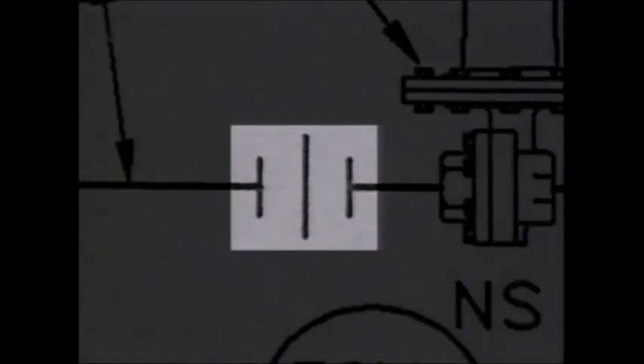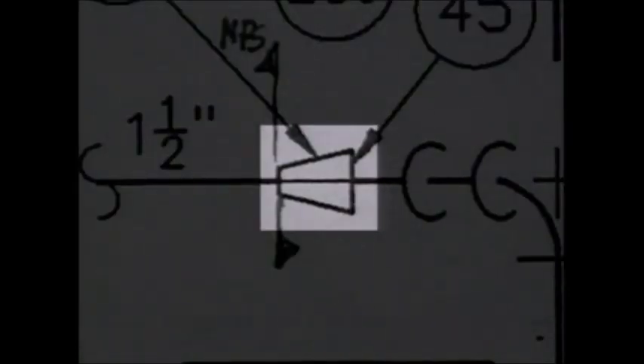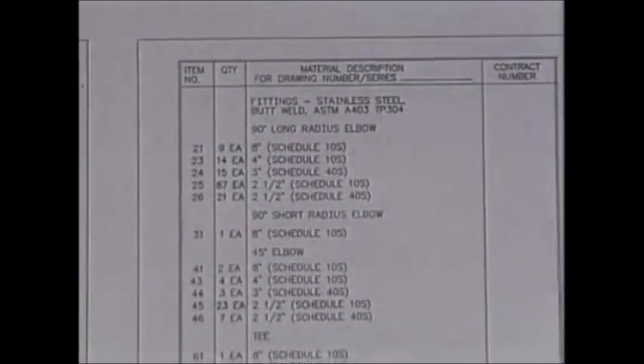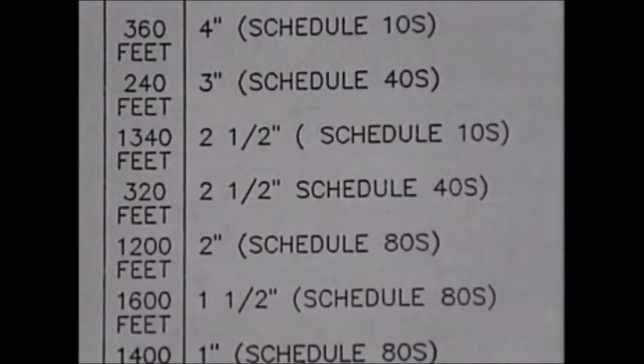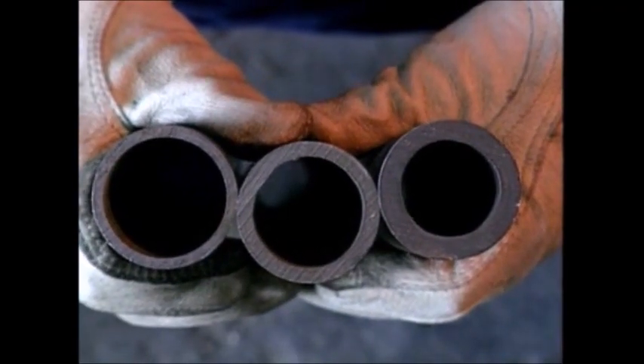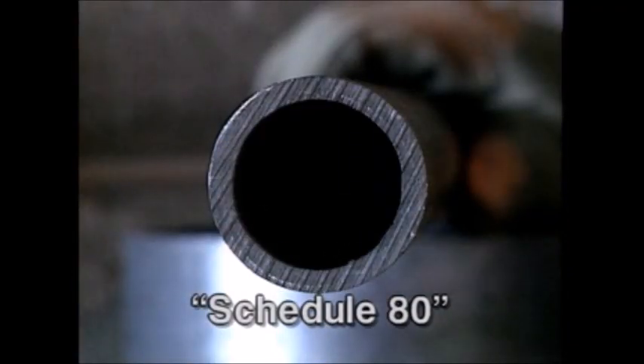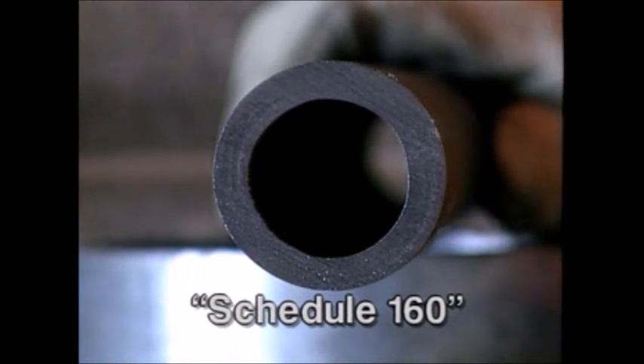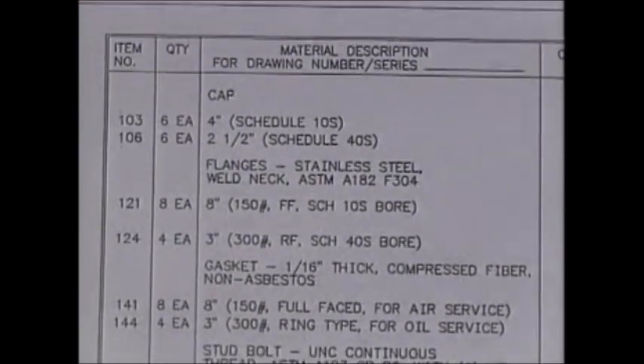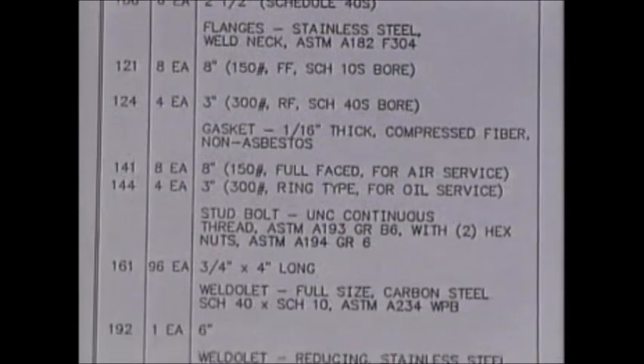Unions are depicted by this symbol, and reducers are indicated by these symbols. Whether the fittings are screwed, welded, or flanged is indicated in the bill of materials, usually on the first print in a series. The bill of materials gives the specification and grade required for all materials, plus the size and schedule. The schedule is the wall thickness of pipe — standard is schedule 40. Schedules 80, 120, and 160 have progressively thicker walls and progressively smaller inside diameters. The material specifications must be adhered to unless engineering okays a substitution.